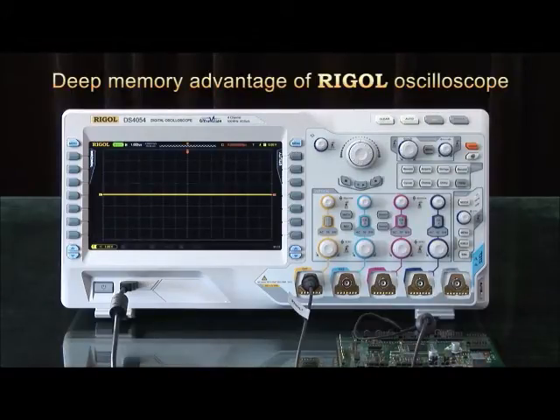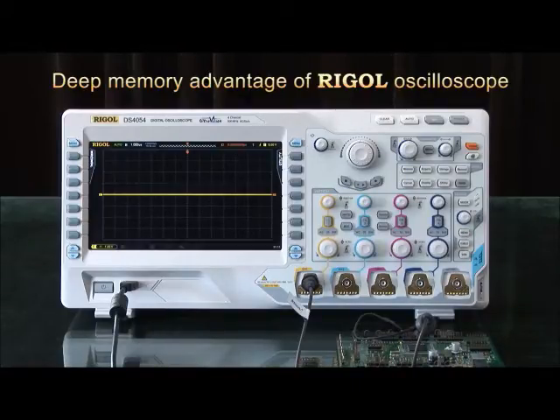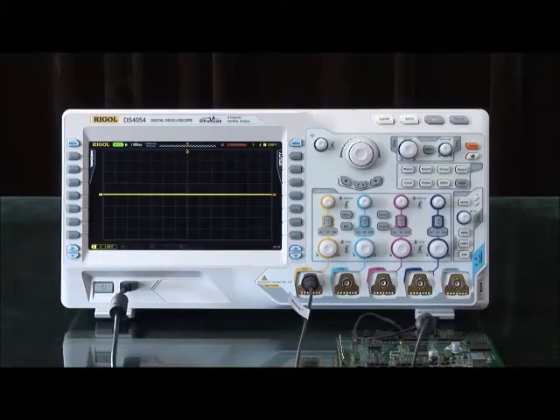Modern digital storage techniques have significantly increased the power of test equipment. Many digital oscilloscopes have storage depths in the kilopoints, with a few instruments reaching up into a megapoint or so. RIGOL oscilloscopes featuring UltraVision technology have storage maximums of 140 million points standard.